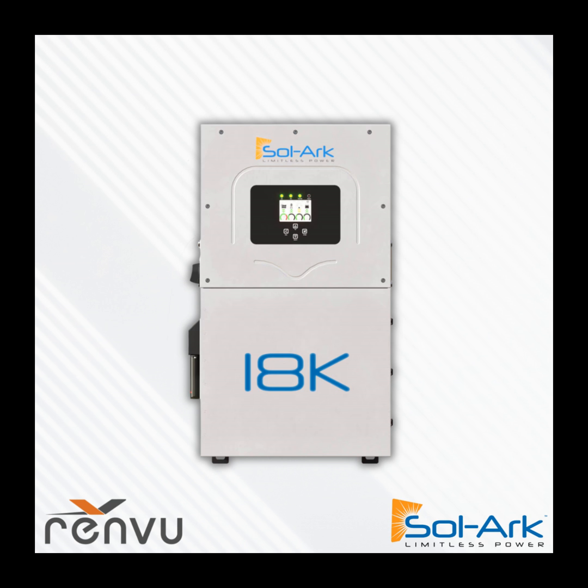...and say, okay, facility manager, now that we're in the control room, which of these distribution feeders is the most important? That's going to be your interconnection point. And if there are 2 distribution feeders that are important, that's all right — you unplug those, plug them into the Sol-Ark, run a new set of home runs from the Sol-Ark to the main service panel, and that's your project.